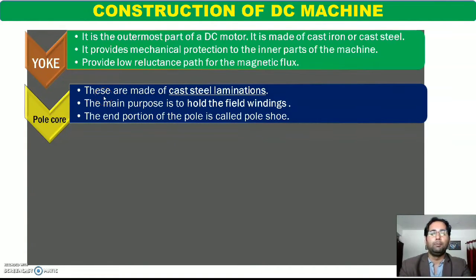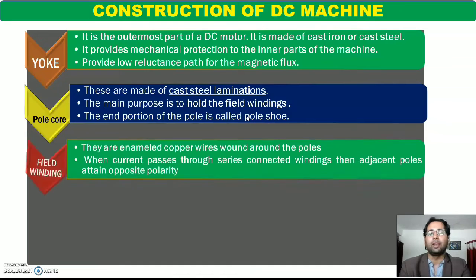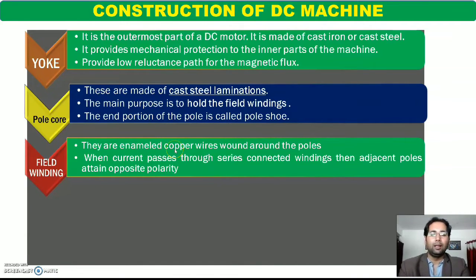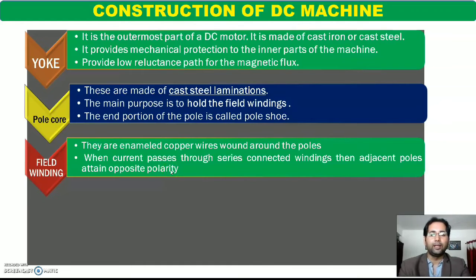दूसरा important part of stator is pole core. Pole core cast steel laminations से बने होते हैं और यह आपस में laminated होते हैं. The main purpose is to hold the field winding — इसी पर हम field winding को wound करते हैं — और यह field winding को low reluctance path, यानि magnetic flux को low reluctance path provide करते हैं. The end portion of the pole is called pole shoe. Pole shoe का जो shape है वो especially curved क्यों होता है — इसलिए होता है ताकि uniform flux generate कर सके. Third important topic is field winding. Field winding laminated enameled copper wire का बना होता है, जो pole के चारों तरफ wound होता है. यह field winding pole to pole series में connected होती है, जिससे adjacent pole पर opposite polarity होती है — एक pole पर north होगा तो adjacent pole पर south होगा.